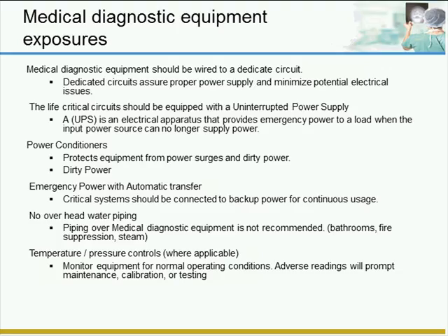Uninterruptible power supplies, UPS systems, should be utilized at all medical facilities. They're slightly different from an emergency generator, where a UPS system will have a battery backup, which will allow the emergency generator to come online so there are no glitches in the system. Power conditioners should be utilized as well. Power conditioners clean the AC power and eliminate interferences on the power lines. You'll commonly find a power conditioner at the main feed of all medical facilities.